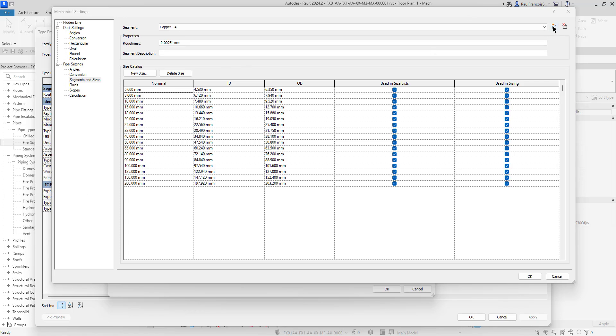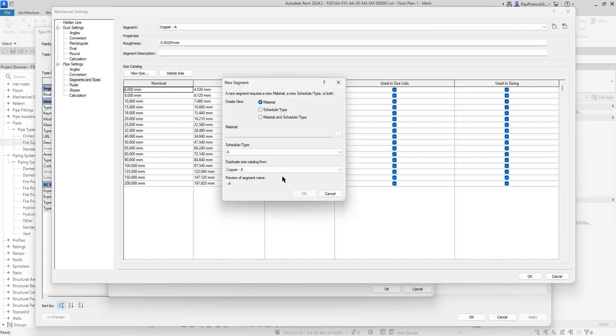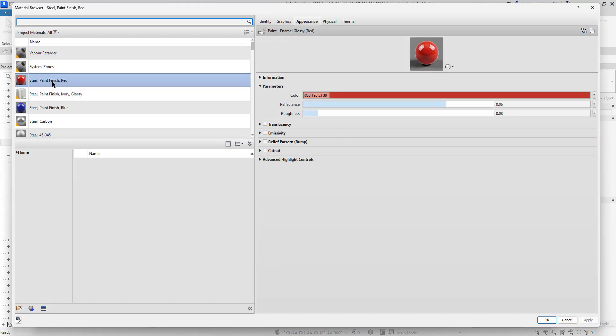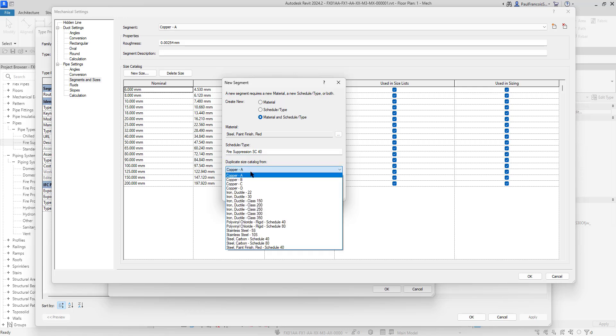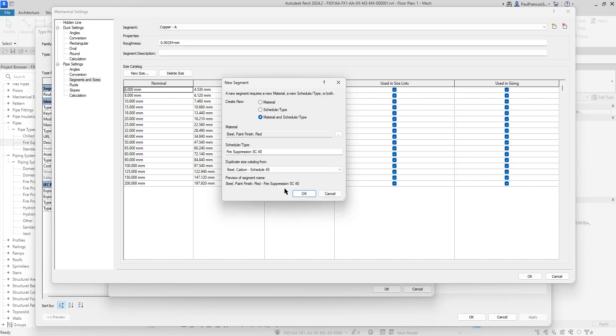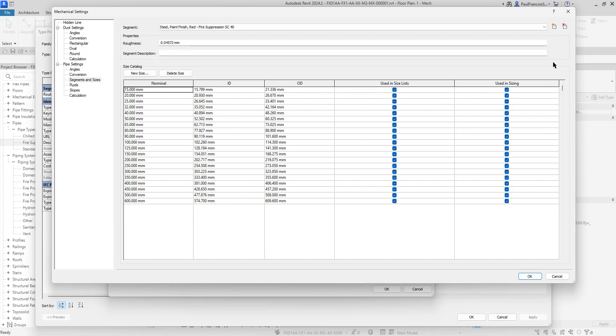What we are going with is the new pipe segment, material and/or schedule type. The material we're going to use is this red material. The schedule type I'm just going to say fire suppression for now. It should be schedule 40. Duplicate the size catalog from steel carbon schedule 40. We can see we've got the steel type, the size catalog, and we can say whether these must be used in sizes.